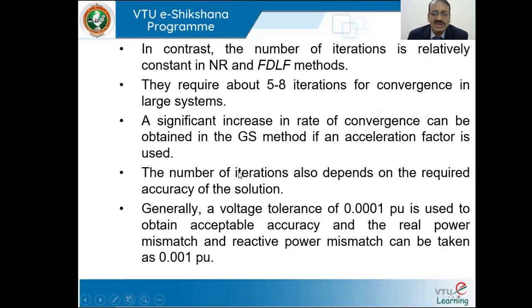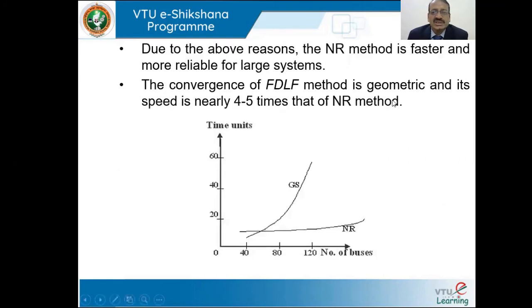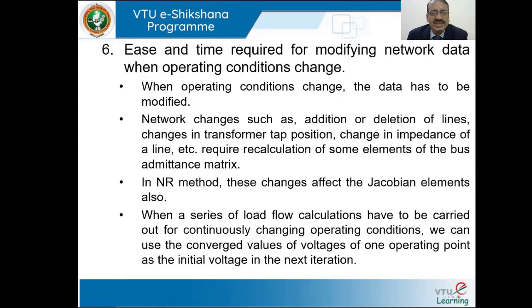A significant increase in rate of convergence can be obtained in the Gauss-Seidel method if an acceleration factor is used. The number of iterations also depends on the required accuracy of the solution. Generally, a voltage tolerance of 0.0001 per unit is used to obtain acceptable accuracy, and the real power mismatch and reactive power mismatch can be taken as 0.001 per unit. Due to these reasons, the NR method is faster and more reliable for large systems. The convergence of the FDLF method is geometric, and its speed is nearly 4 to 5 times that of the NR method.